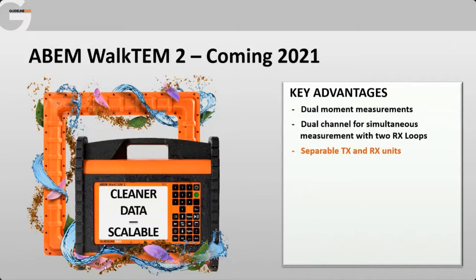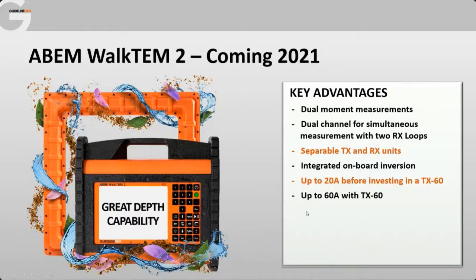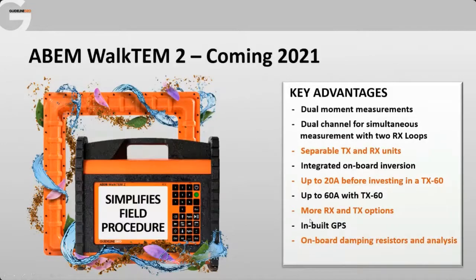And that allows us some advantages because that allows us to set up more options in terms of the scale of the instrument. You know, the price range can be broader, the specifications can be broader, but it also reduces signal noise even further than we managed to get it on the WalkTEM 1, which is exciting. We still have the onboard inversion, so you can still process your data while you're in the field. We're now going to be able to get up to 20 amps before you actually need to invest in a TX60. So we've kind of stretched the capability of the transmitters that we have. As I said, more receiver options, more transmitter options, so easier to find a system that is suited to your needs or your budget. Still got an inbuilt GPS, the same as all of the ABEM instruments, so you will always know where you were measuring.